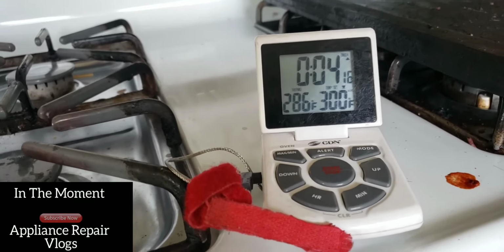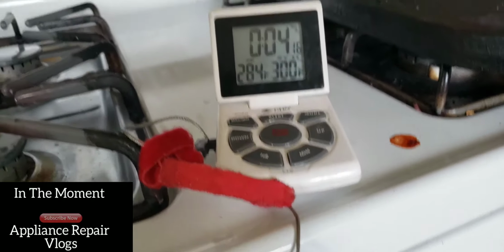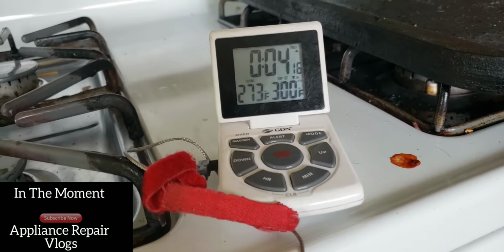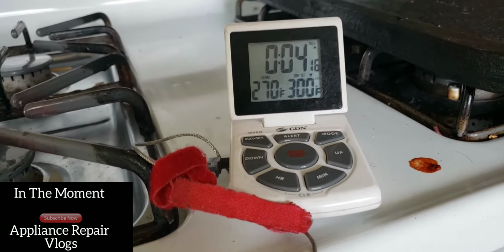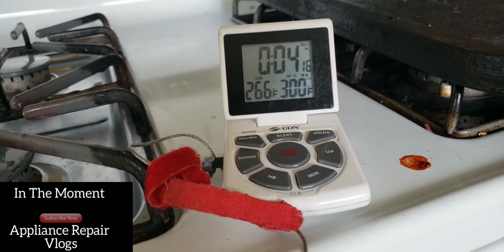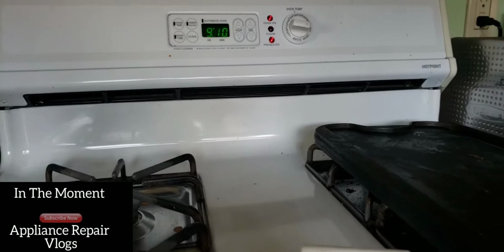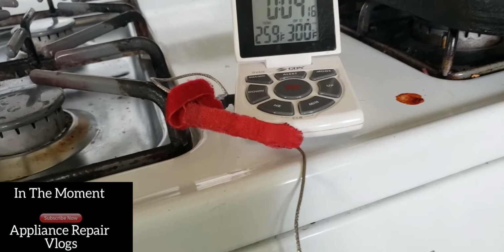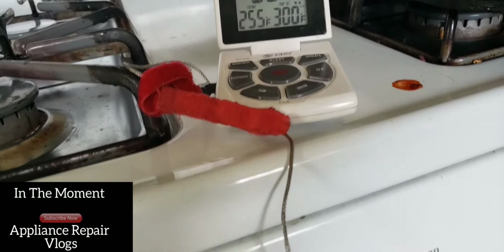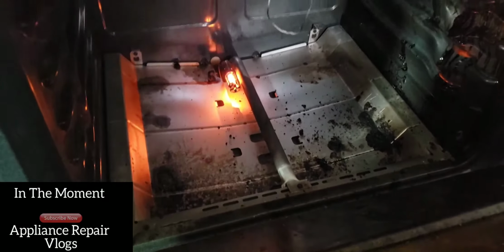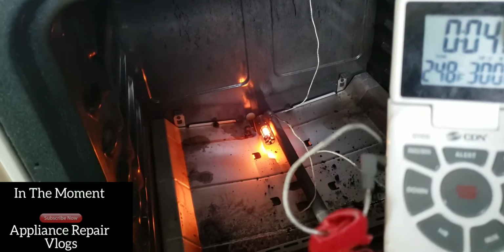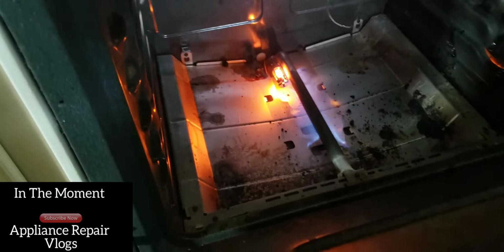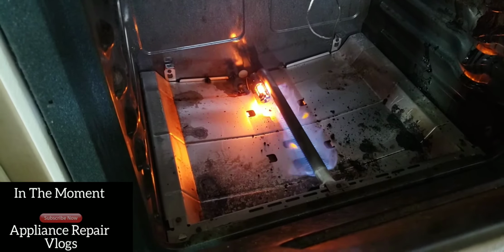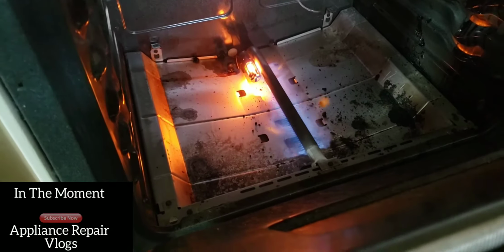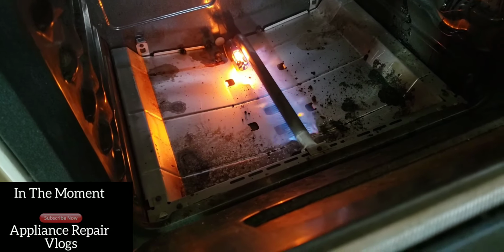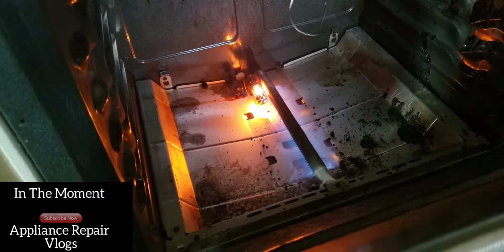Should cool down 25 degrees less than desired temperature, and igniter should regain power to ground from the thermostat. That verifies that the probe is working properly, and power to ground to the dial thermostat. Power to ground to the igniter re-engaged at 240. Ignition system re-engaged. Combustion temperature reached once again. Gas is allowed to flow through the regulator, combusting on the igniter. Igniter is reaching combusting temperature.